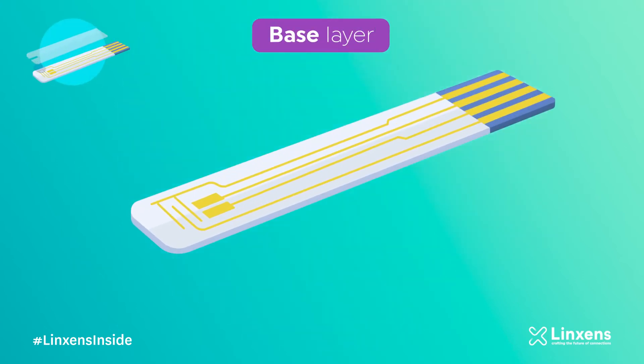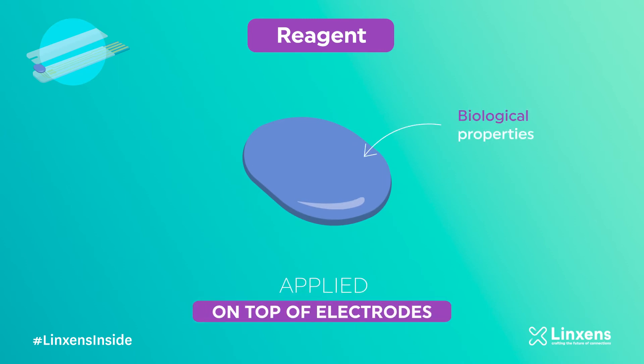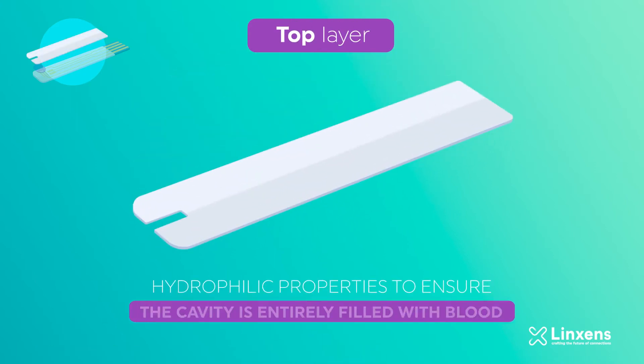The base layer contains Linxens transducer material which has gold electrodes to ensure rapid and accurate measurement of the blood. A reagent with biological properties is applied on top of the electrodes and reacts with the blood. The top layer has hydrophilic properties and ensures that the cavity is entirely filled with blood.